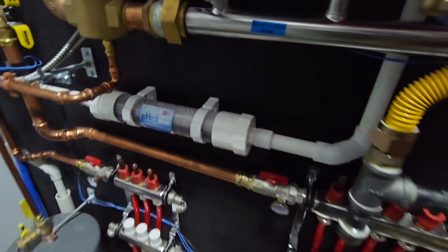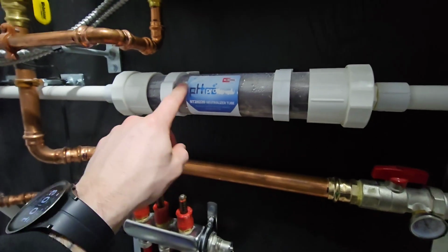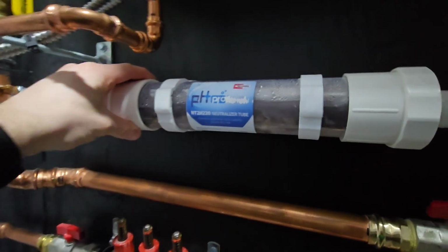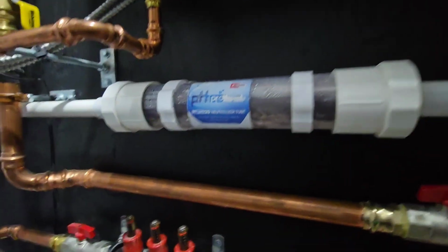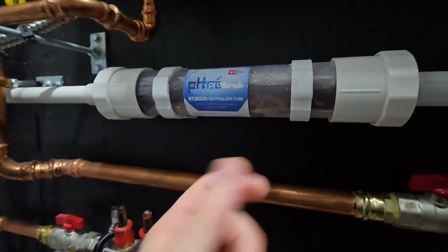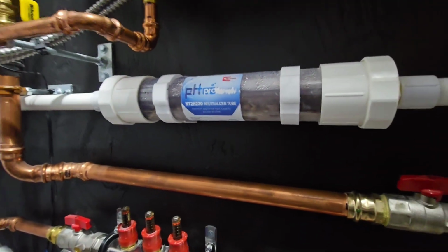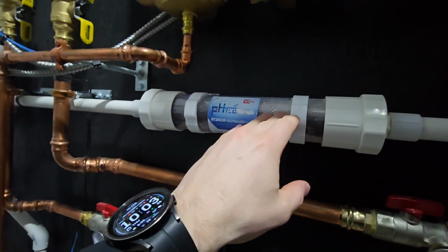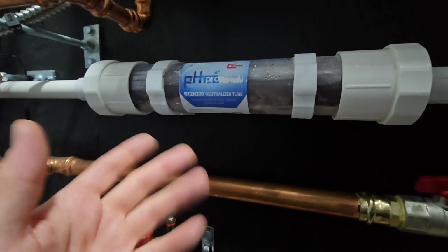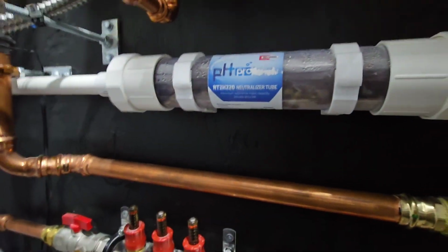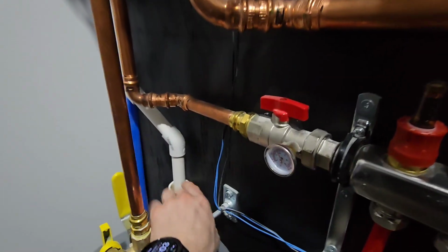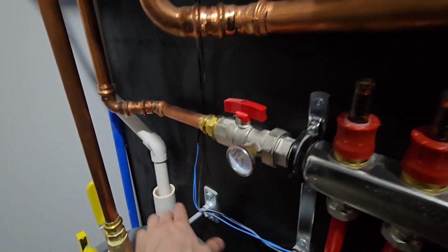So when that water enters into this component here, it's going to be saturated with this inside and all around this media. What's in there is basically just a little bag of media that's going to neutralize that water. And then what it's going to do is fill up to a certain level, spill over, and then come out. So you do want that water to sit in there a while in order to have its reaction that it needs to go through. And then it will drain, and right now I actually have this just draining into my septic system.